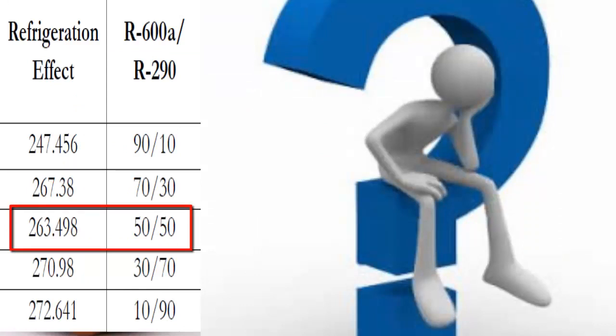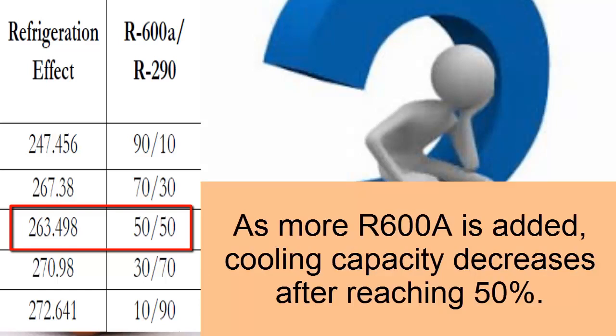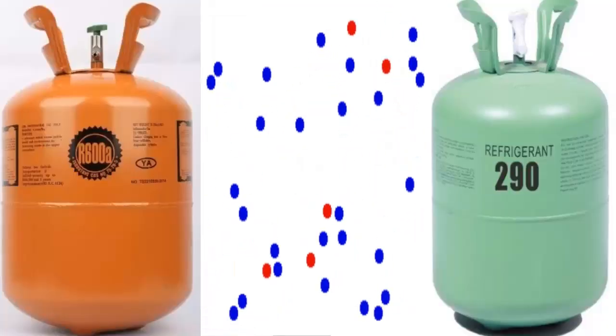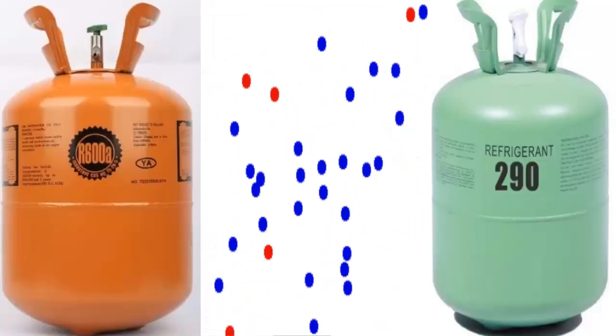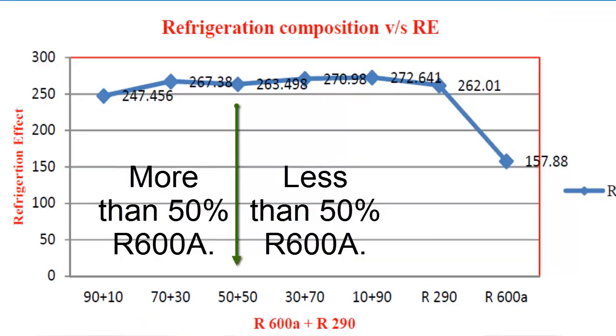As the amount of R600A increases in the mixture, with values well above 50% of R600A, the cooling capacity or refrigeration power of the system starts to decrease. In other words, it takes more time to cool down, or has the ability to cool down fewer products. On the screen we have different cooling power values for some mixtures between R600A and R290.